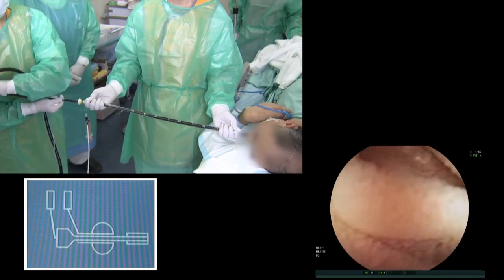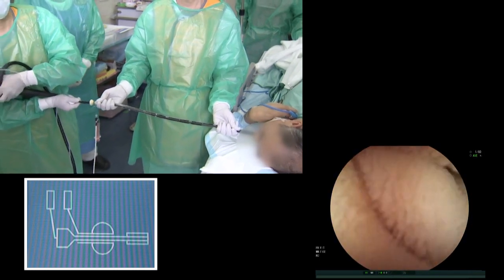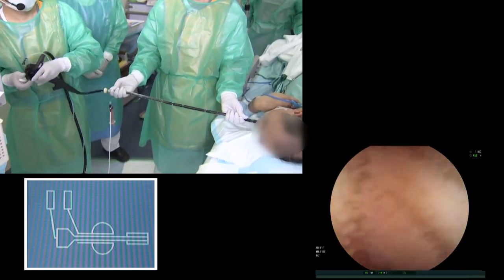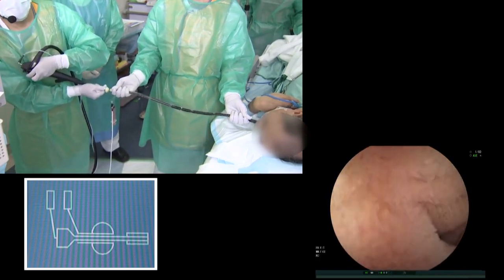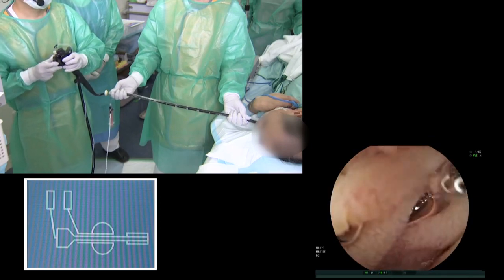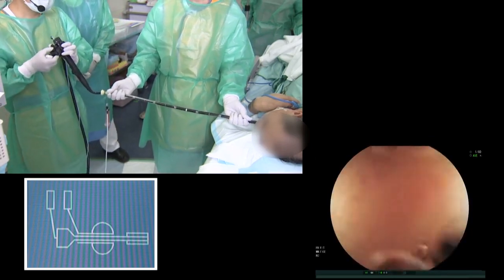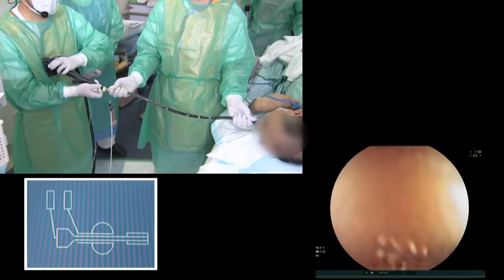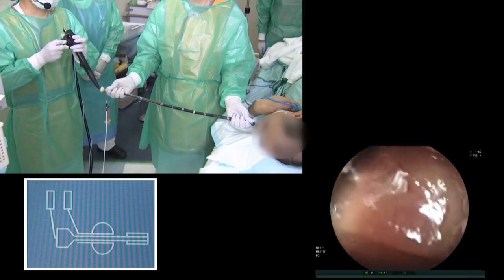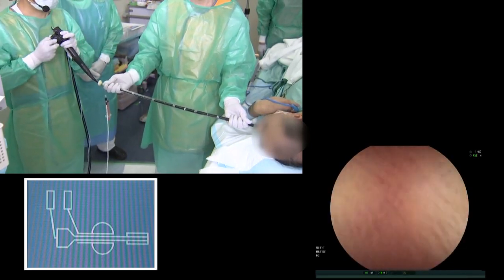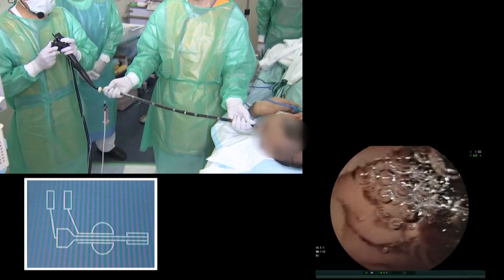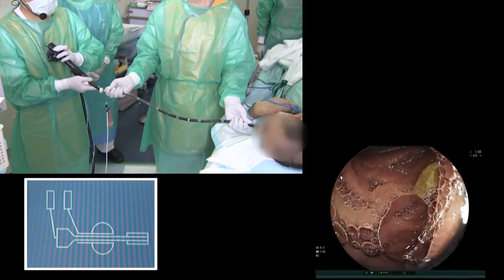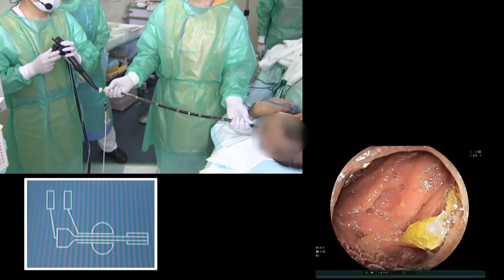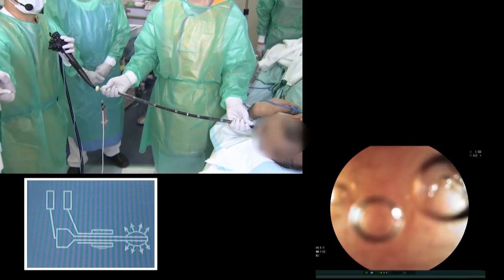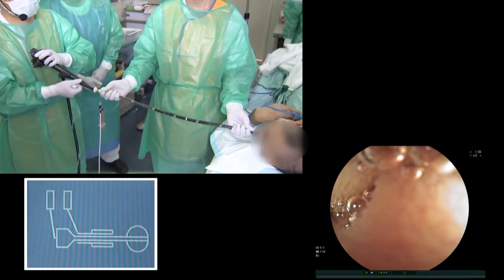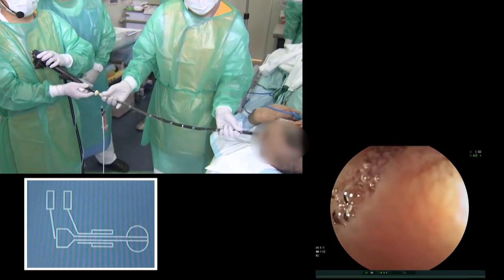The pressure of the DBE balloon is designed for extremely low pressures, 45 mm Hg, which significantly limits the gripping force. The key to insertion of DBE is that the insertion goes well under conditions of such low gripping force. We do not want to simply push the endoscope in regardless of the form. Rather, we want to adjust the shape of the intestine that would enable easier insertion and use a balloon to retain this adjusted shape. Also, ideally we want to use the minimum insertion force required. Thinking about the endoscope in this way will help perform a safe and effective insertion. 30 centimeters. All right, advance the overtube.